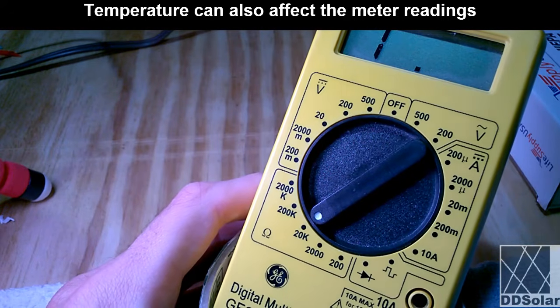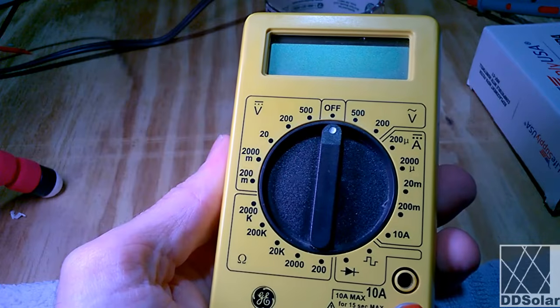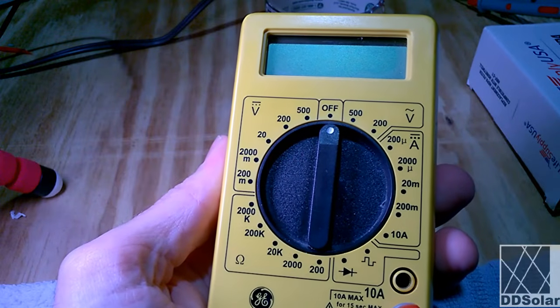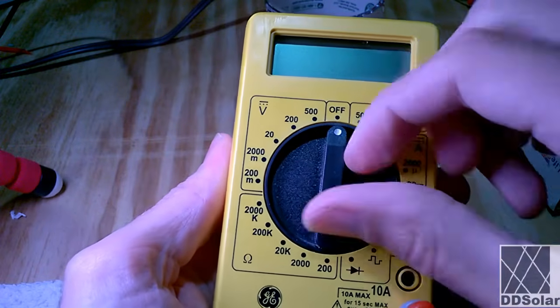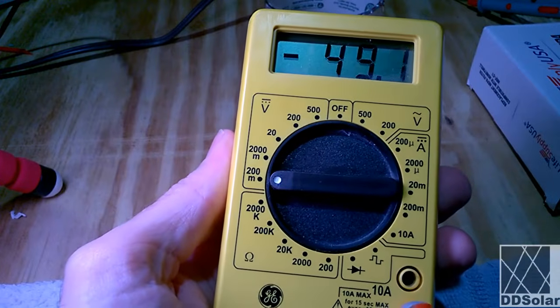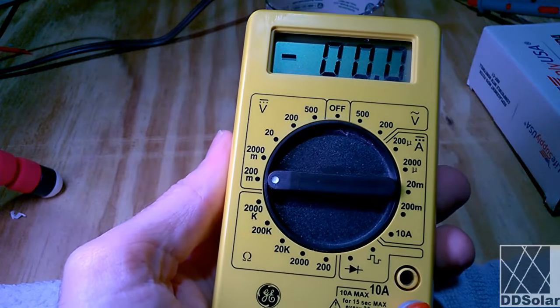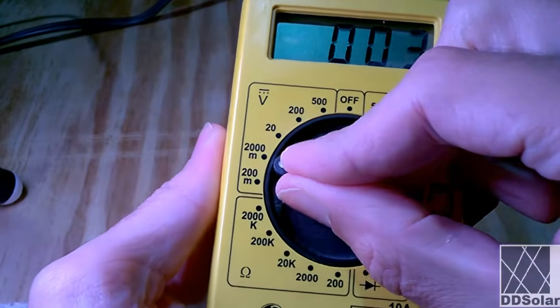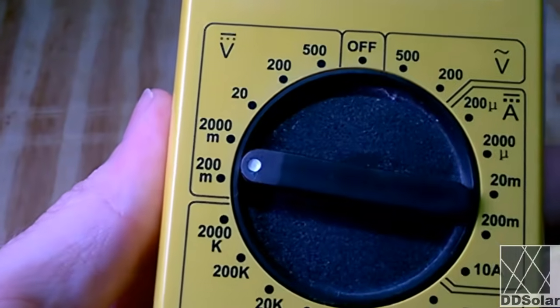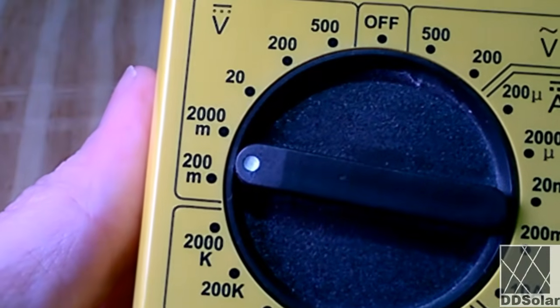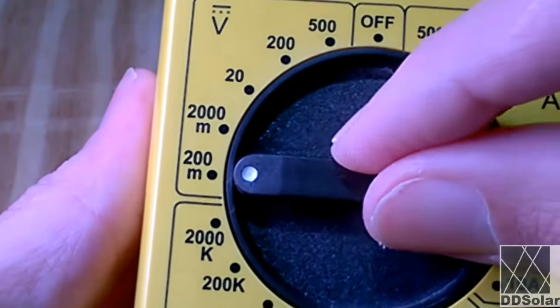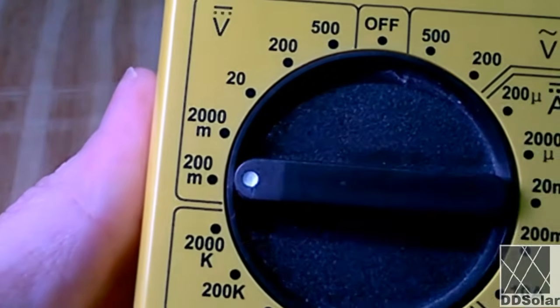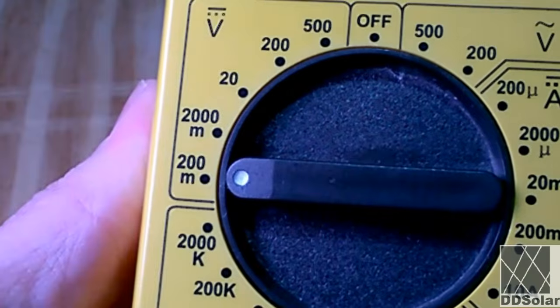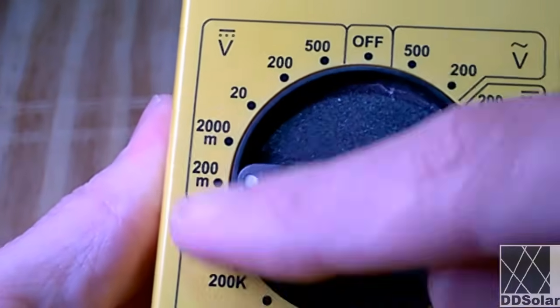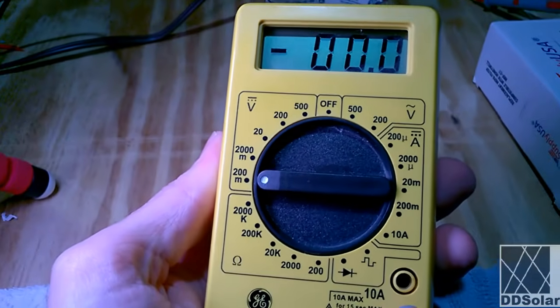Another obscure fact about this type of multimeter is it's very common that people will just take the dial and flip it over to what they want, and they don't pay a lot of attention. It's very possible that the meter can get stuck in between. So you can see right there, I've stopped it in between two different settings. If you do that, the contacts inside this rotary dial may not give you the results you expect, since this dial is actually part of the circuit inside the meter.